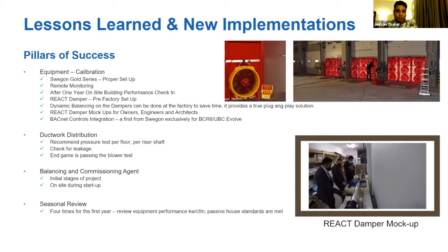So with balancing and commissioning, what we realized is that having the right tool is a game changer. You can't just use your standard tools in construction. I pick on a hospital using instruments at a diffuser versus a Passive House. You need to be able to measure 60 CFM, 110 CFM.